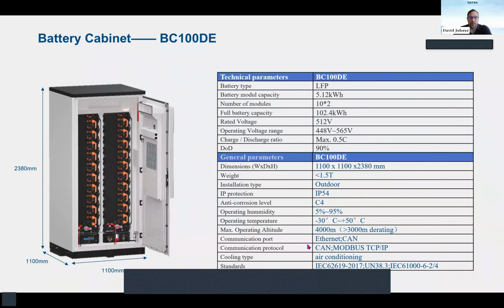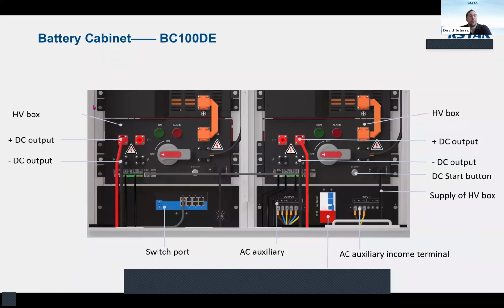Regarding the communication protocol, it can be operated through CAN, Modbus or TCP/IP protocols, and it conforms to the global standards. Regarding the battery cabinets, it is the bottom of the battery cabinets, and regarding the controlling, it has the rotary switch for switching the battery packs on and off, and it has a DC output for each cluster. The other connection point is where you can put the cubicles or the cabinets in parallel.